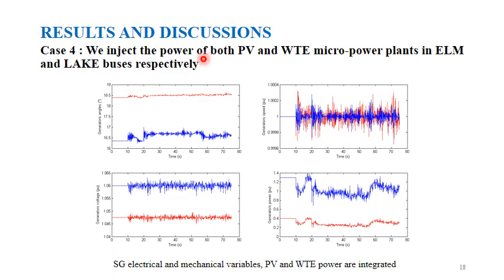The last case is when we inject the power of both the PV and wind turbine emulator micropower plants at the ELM and lake buses respectively. It is clear that the disturbances generated by the intermittent injected powers propagate rapidly to the grid, affecting both generators. The power system stabilizers present a fast reaction to power mismatch, keeping voltage and speed at their nominal values for each disturbance. Comparing cases 2, 3, and 4, we conclude that it is not the quantity of injected power that causes important disturbances, but rather the sudden increases or decreases. In case 4, the disturbances are the same as in case 3; however, the power generated from both synchronous generators is reduced much more in case 4 compared to cases 2 and 3.